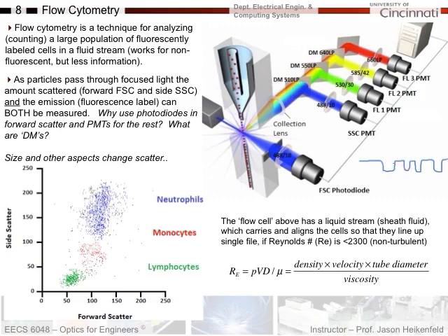So every time the light intensity went down versus time, that meant a cell was getting in the way of the beam path. The reason you can use a photodiode for this is that you have a laser, plenty of optical power, right? But how much light can you get to fluoresce off a cell? Not very much, so that's why you need these photomultiplier tubes.